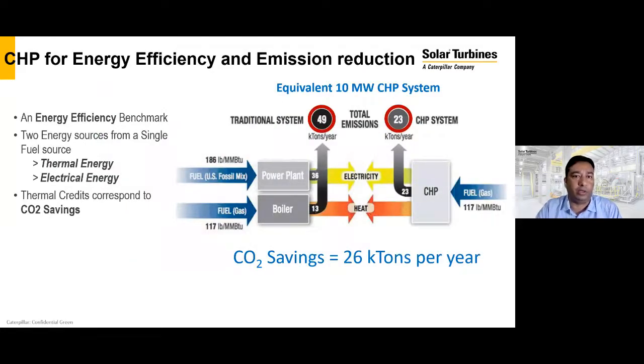So coming to the topic, why should customers go for CHP? The reason is basically energy efficiency with a CHP and the emission reduction benefits. The traditional system will have a grid where a power plant is far away with T&D losses, burning some fossil fuel, and the customer is using a boiler with a gas fuel to meet his heat requirement. In that way, the traditional system will generate something like 49,000 tons per year of carbon emission.